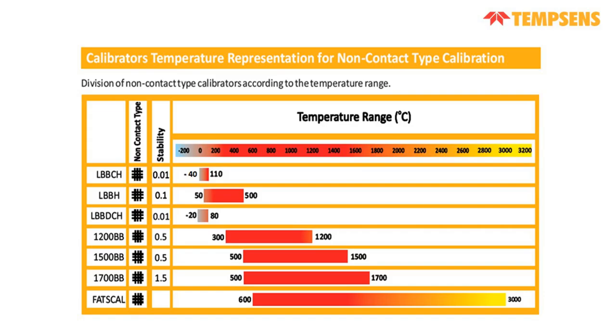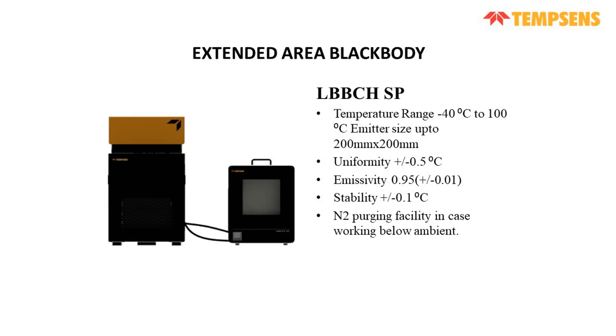So this is the calibration range that we have, from -40 to 3000°. This is the LBB CH-SP, and the temperature range for this model is -40 to 100°. It comes with a chiller unit, and then we can have a uniform temperature over the emitter, with uniformity of plus minus 0.5°, emissivity of 0.95 with plus minus 0.01, and stability of plus minus 0.1°.